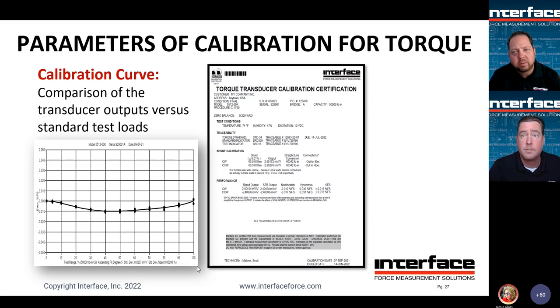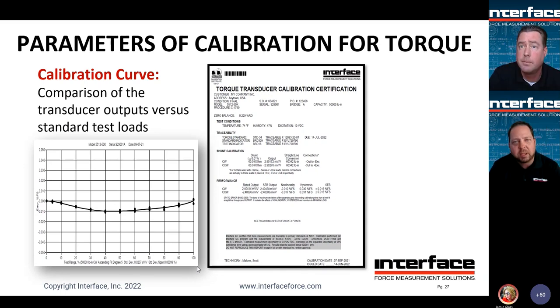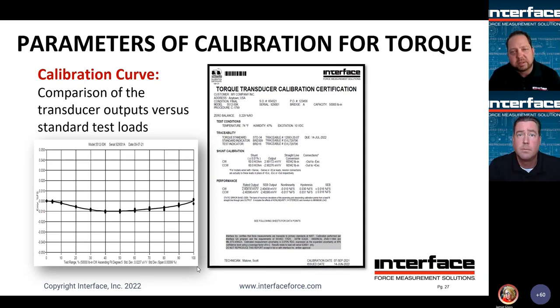E2428, what is this standard again, Elliot? E2428. There we go. Thank you. So this is equivalent to an ASTM E74 for a load cell. This would be a snippet from a more extended test report that you would get than just the standard points. But the key there is, of course, that you do get a slight non-linear output from a sensor.